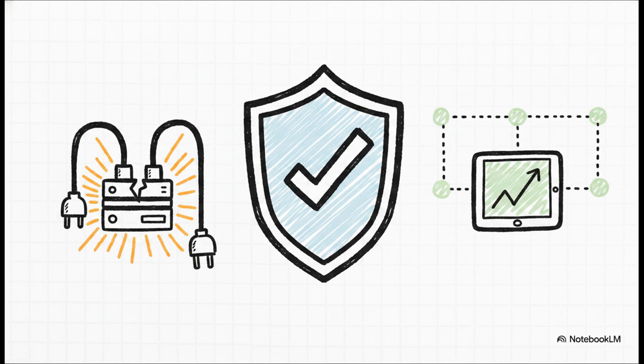Well, Supermicro guarantees maximized uptime through built-in redundancy. The sidecar comes with redundant power supply units, or PSUs, and an automatic transfer switch. So if one power source drops, the cooling doesn't even blink, it just keeps running during critical power disruptions.